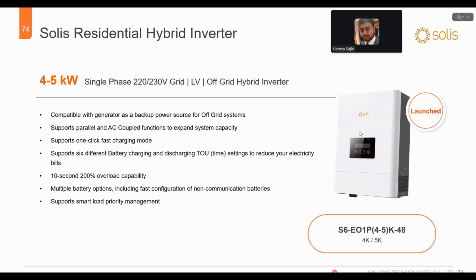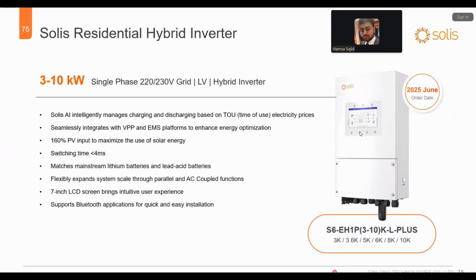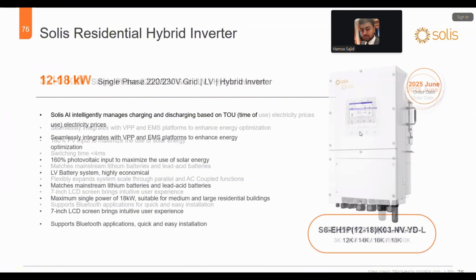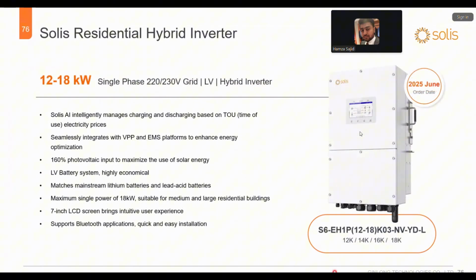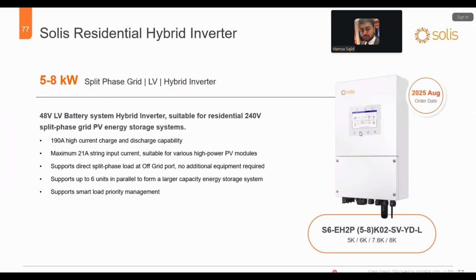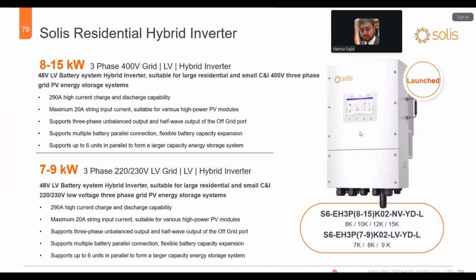This is the IP21 4 to 5 kilowatt inverter, single phase low voltage, and this was the 3 kilowatt to 10 kilowatt single phase low voltage inverter available with the LCD. And this is from 12 to 18, where the system has single phase wiring inside and the load is too high, they cannot change the house internal wiring, so they can use this single phase one. Then we have the 3-phase one. This is the split phase one. Okay, these are the 3-phase ones we already have launched, and they are the hot items available in other markets right now.